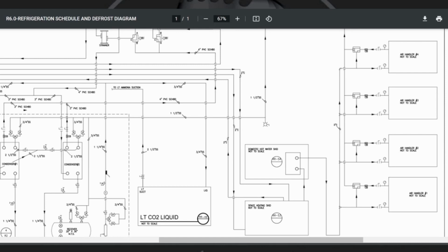Oh, excuse me, I take that back. This represents all of the different heating loads. There's only one stage of heating in the main air handler, and you have a 3-way valve. You're moving your desuperheater water all the time up through that air fluid cooler. So when you want heat, all you do is operate a 3-way valve, and the hot water flows through the air handler. When you don't want heat, the hot water bypasses the air handler, and then the heat is rejected through the air fluid cooler. Summer and winter, doesn't matter.